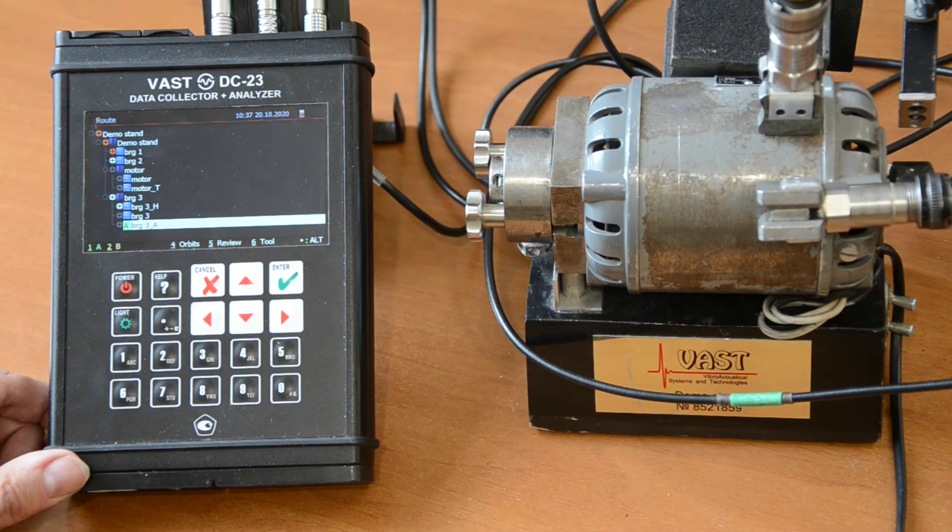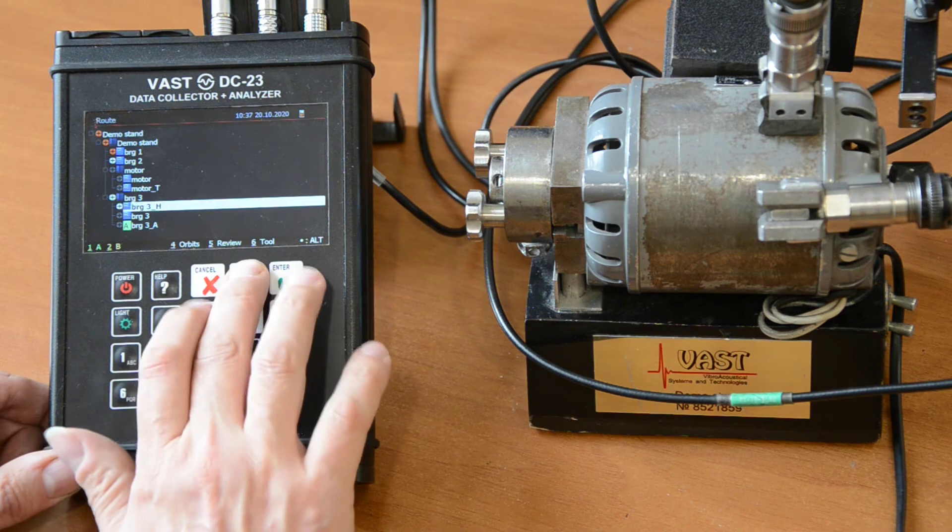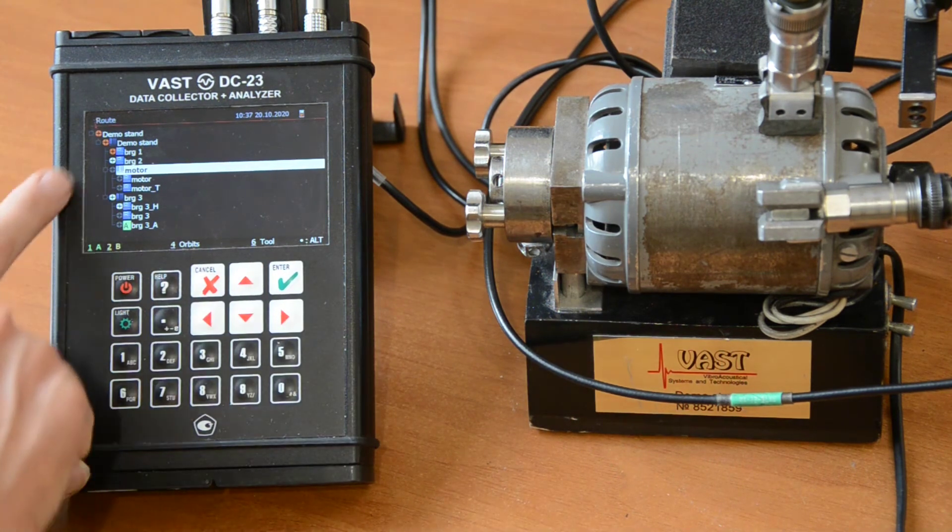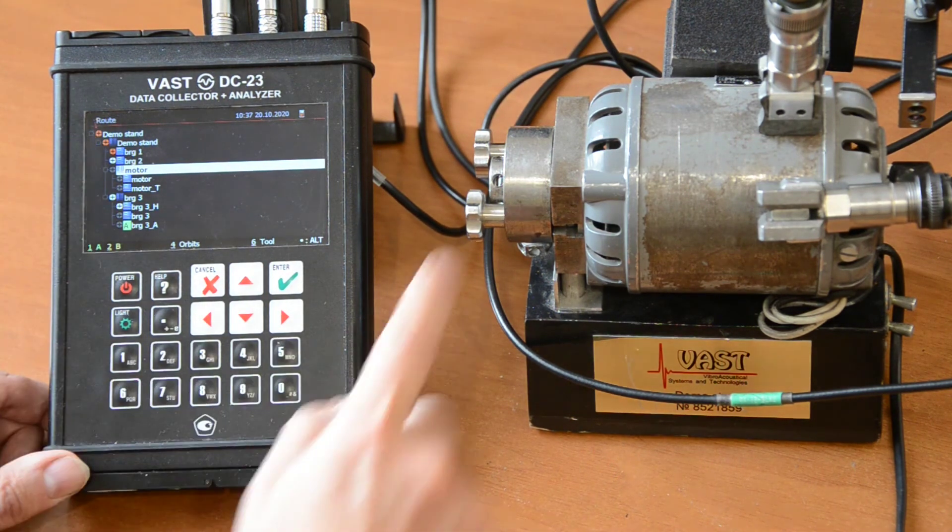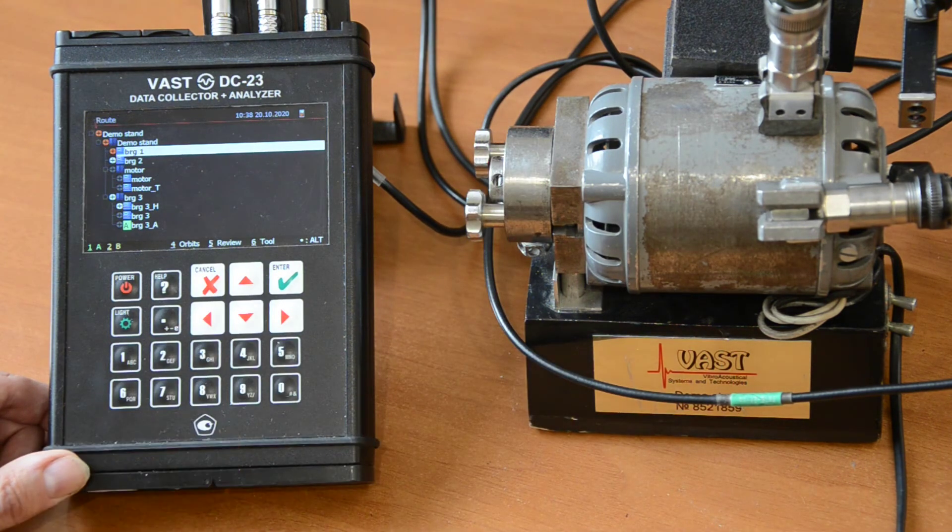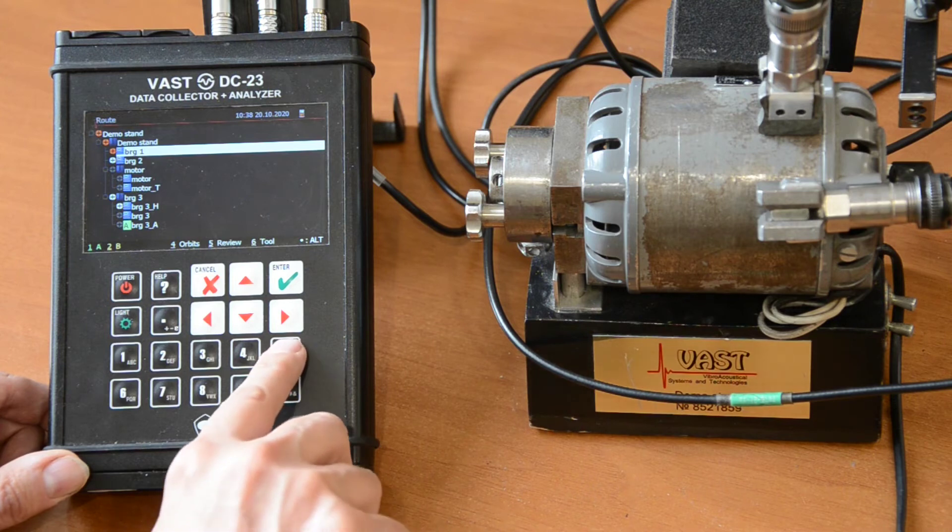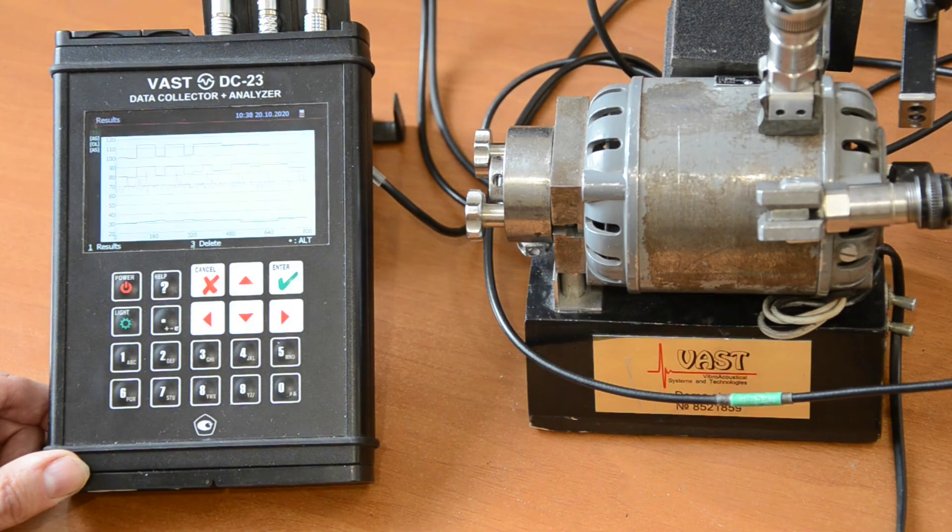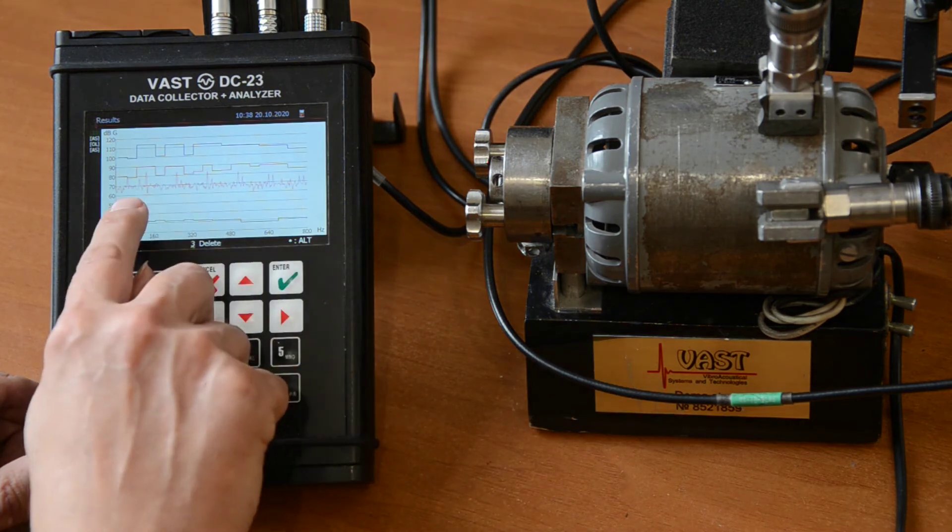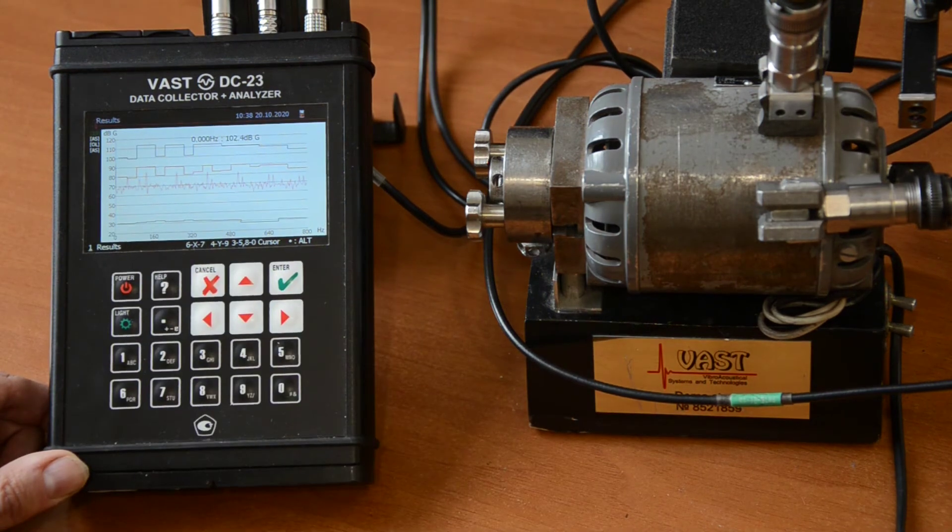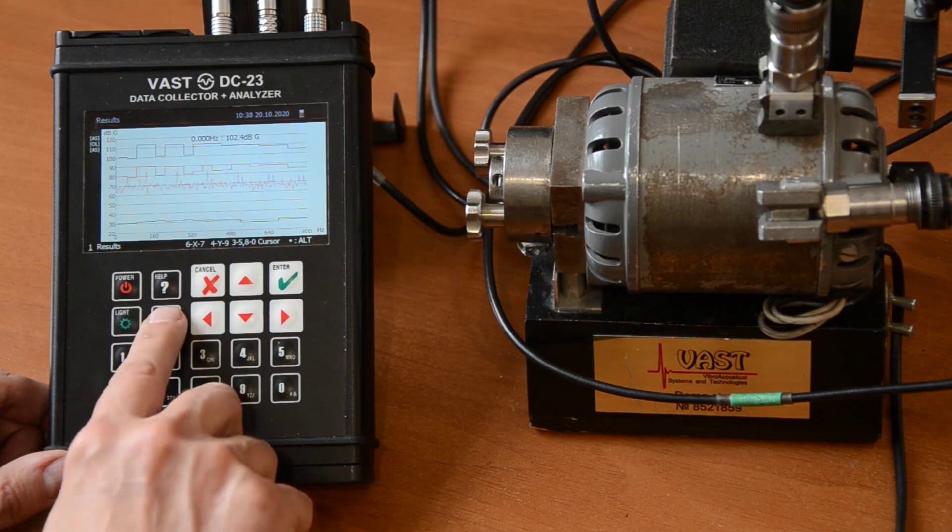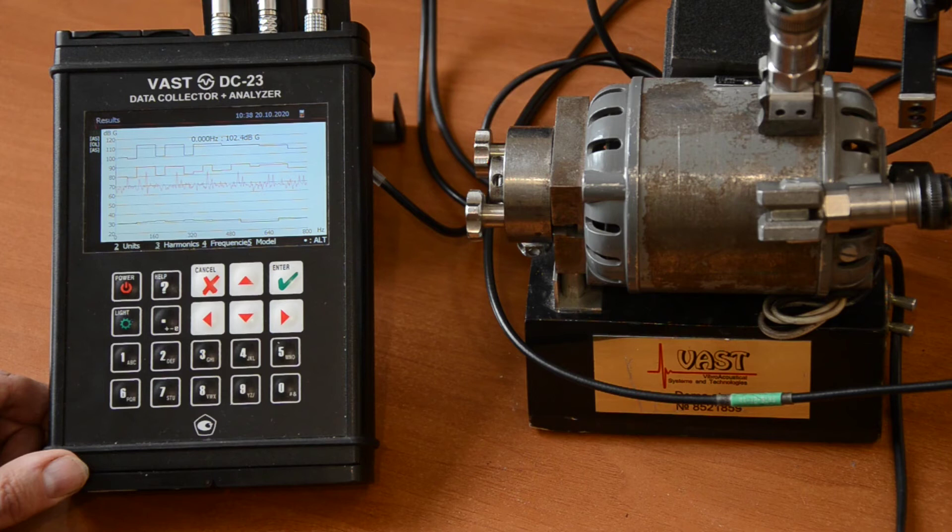So, here we have completely finished our route collection. And we can see that the only problem that we have here is in the Bearing 1. That is this Bearing. And we can do also some analysis in field. For this, we go to the review. We look at this spectrum.